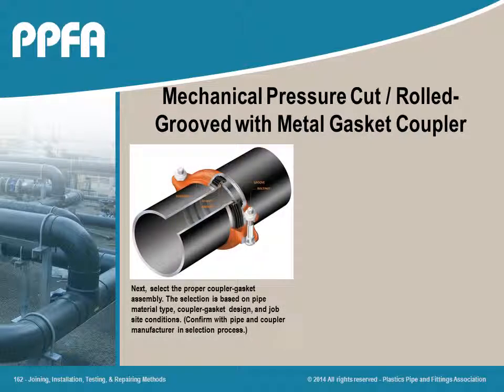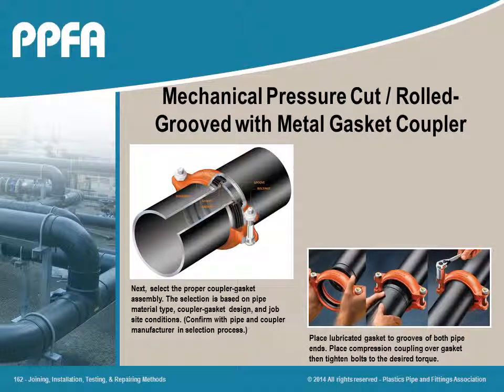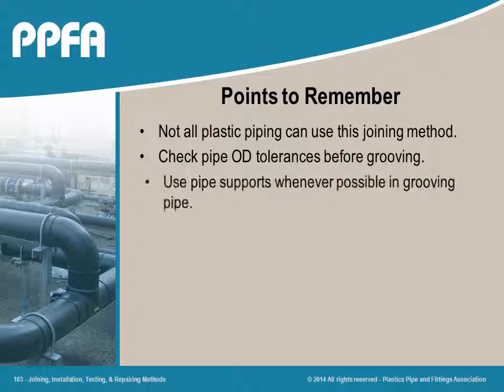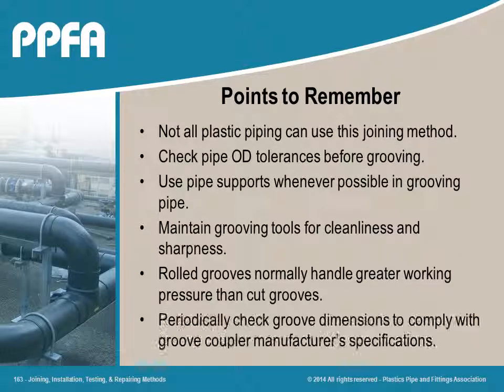Several pipe suppliers can supply groove pipe ends to simplify and reduce labor requirements. Check with the piping system provider to determine if there will be any derating of the pipe working pressure. Also, make certain that the coupling elastomer is compatible to the fluid being handled. Grooving machines can be purchased or rented.